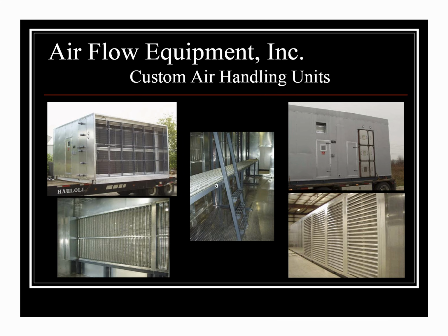This middle picture shows a service platform for a filter rack. You get into filter racks being maybe 5 high, up 10 foot, 120 inches. Getting up there to service that top row of filters becomes rather challenging. Obviously somebody would need to take a ladder into the air handling unit. Or something we've done is build a catwalk that somebody can go into the unit, crawl up, go up this fixed ladder, and then replace their upper bank of filters. We've also used a rolling ladder, like a library rolling ladder, to get access to upper banks of filters. That type of stuff is all doable upon request.